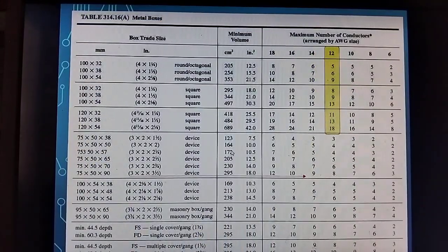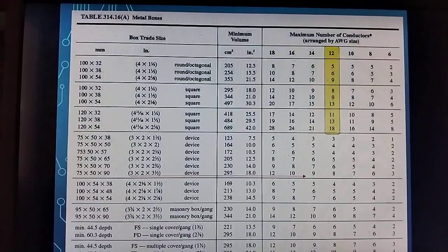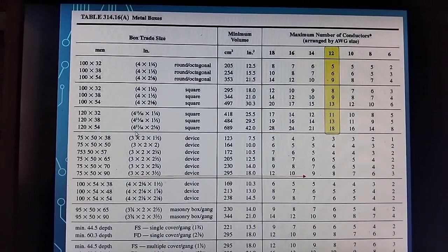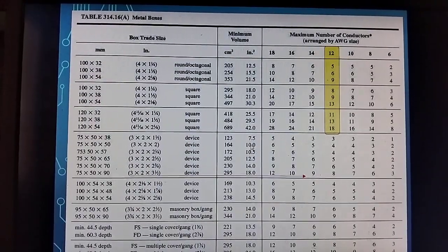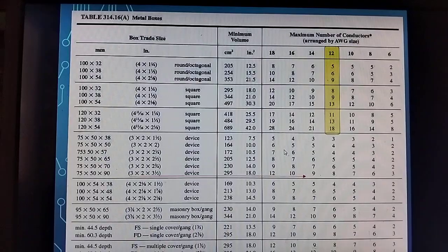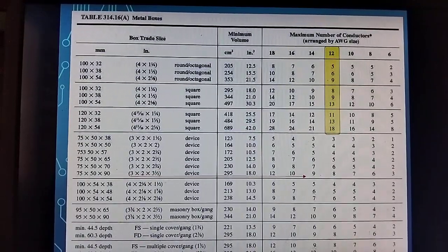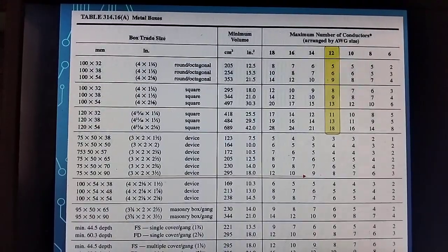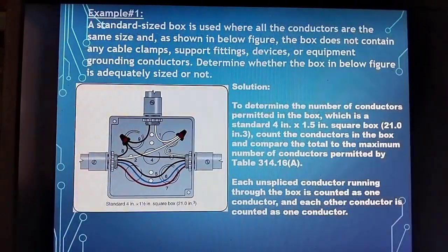If we go to the standard, say size 14, the biggest is 4 and 11/16 by 2 and 1/8 square. The cubic inch capacity is 42. Now let's say you already installed the junction box, and you have to connect all wirings. Make sure you have adequate allowance for splicing, because I have a suggestion here.